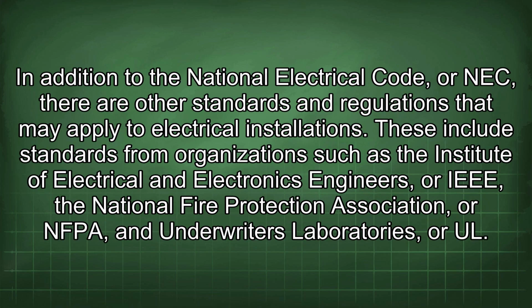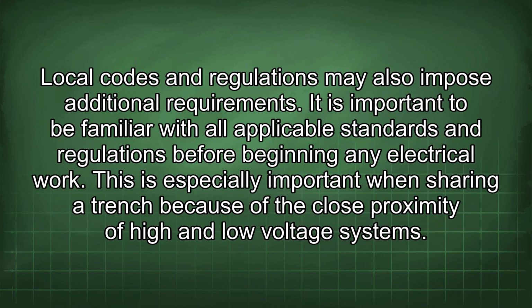In addition to the National Electrical Code, or NEC, there are other standards and regulations that may apply to electrical installations. These include standards from organizations such as the Institute of Electrical and Electronics Engineers, or IEEE, the National Fire Protection Association, or NFPA, and Underwriters Laboratories, or UL. Local codes and regulations may also impose additional requirements. It is important to be familiar with all applicable standards and regulations before beginning any electrical work. This is especially important when sharing a trench because of the close proximity of high and low voltage systems.